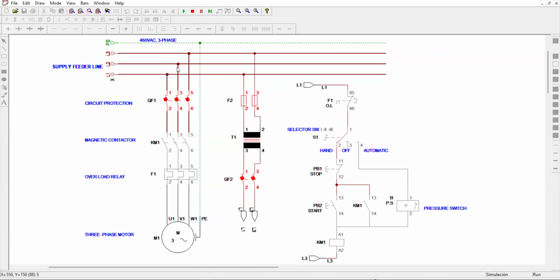This will be our power circuit diagram here on the left side. In the right side, what we call the control circuit diagram. So let's analyze if the circuit is fully functional, on how the automatic operates in a motor control circuit diagram. Once we activate the disconnecting fuse and circuit breakers, we will notice that our motor is not yet activated. This selector switch will indicate your current position, which will be our control to make it manual and automatic.